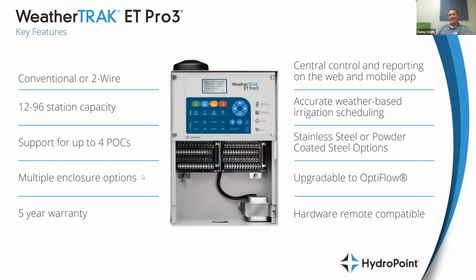So it's very feasible. Ben, correct me if I'm wrong, I believe it's like you said, 36 station or above can take in the second POC. So if you have 2 12-station controllers with 2 POCs, that's not going to work. You're going to have to, correct me if I'm wrong, put in, say, a 42 station controller, going beyond the capacity of the low voltage just so we can get the second POC, even if we're only running 18 valves or so?